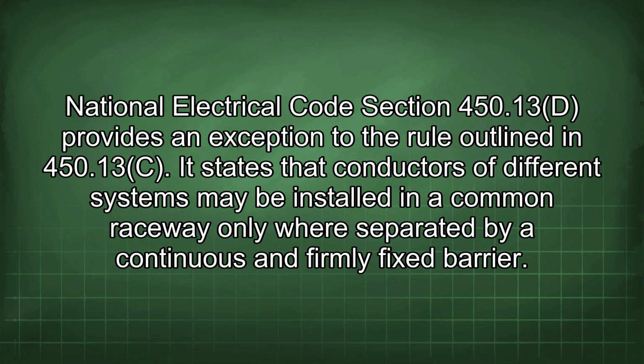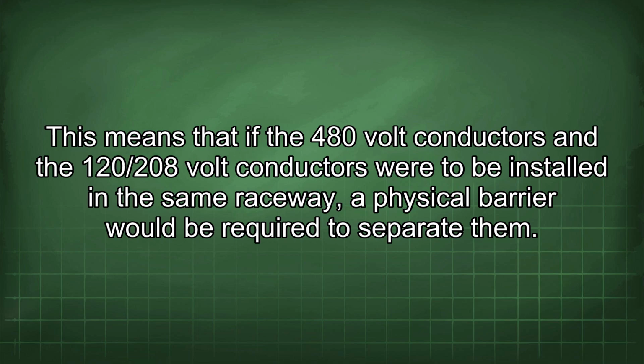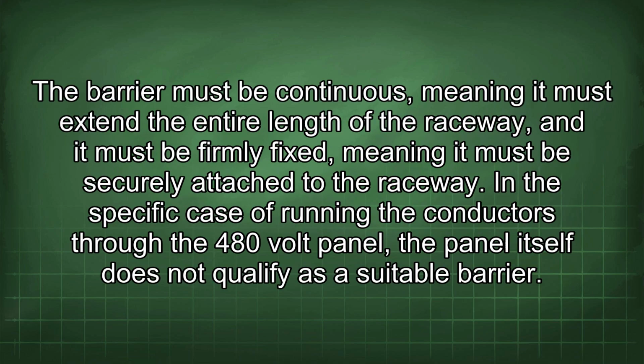National Electrical Code Section 450.13d provides an exception to the rule outlined in 450.13c. It states that conductors of different systems may be installed in a common raceway only where separated by a continuous and firmly fixed barrier. This means that if the 480 volt conductors and the 120/208 volt conductors were to be installed in the same raceway, a physical barrier would be required to separate them. The barrier must be continuous, meaning it must extend the entire length of the raceway, and it must be firmly fixed, meaning it must be securely attached to the raceway.